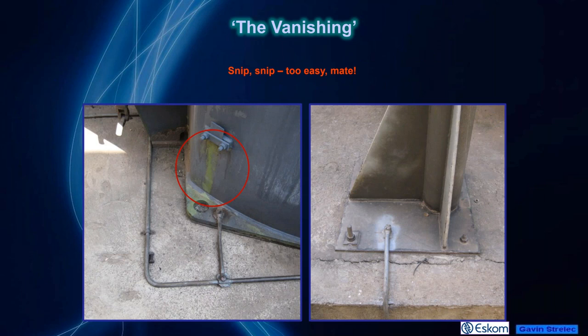Another successful approach used for several decades now is to use copper-plated earth rods. Copper is relatively soft and very easy to cut. Any accessible copper is easily removed within a very short period of time. Criminals usually don't bother to remove it completely. They will just cut off the parts that are easily obtainable, and you can see evidence of the copper flat bar that has been removed, subsequently replaced with earth rods, and those have been in place for many years, completely untouched.